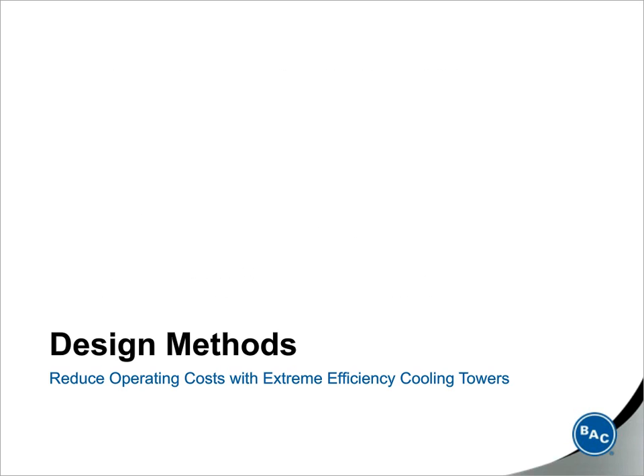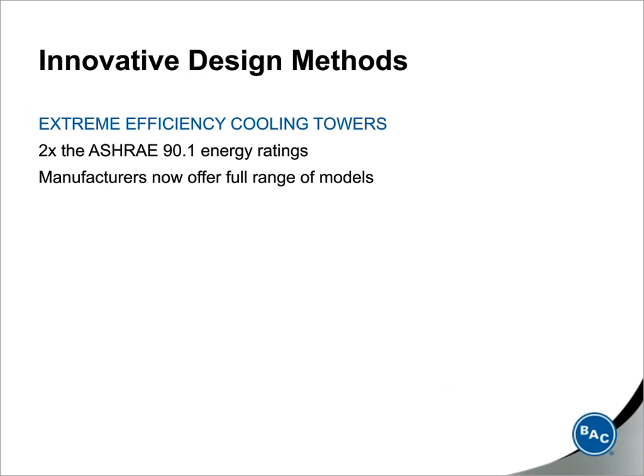Let's move on to the next design method, which is selecting cooling towers with extremely high energy efficiency. Now, BAC defines extreme efficiency towers as having at least 2 times the ASHRAE 90.1 2013 energy rating. Now, cooling tower manufacturers in general, most manufacturers now offer extreme efficiency models with a very broad range of fan motor horsepower, and this actually makes the selection process very, very easy because by simply selecting a cooling tower with more surface area, which is generally going to be a tower that has more efficient heat transfer surface, or it can be a taller unit or one with a larger footprint, it's very easy to evaluate and identify which tower is going to give you higher efficiency.